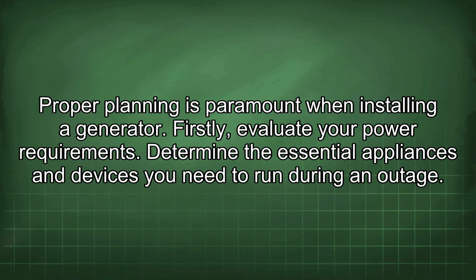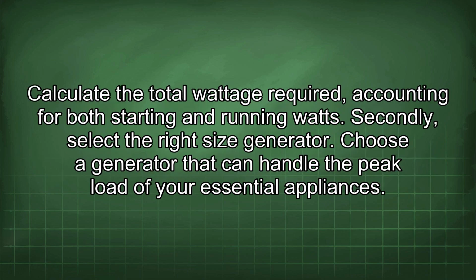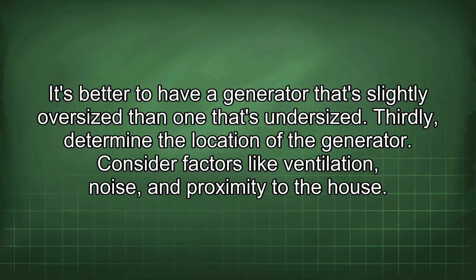Proper planning is paramount when installing a generator. Firstly, evaluate your power requirements. Determine the essential appliances and devices you need to run during an outage. Calculate the total wattage required, accounting for both starting and running watts. Secondly, select the right size generator. Choose a generator that can handle the peak load of your essential appliances. It's better to have a generator that's slightly oversized than one that's undersized.